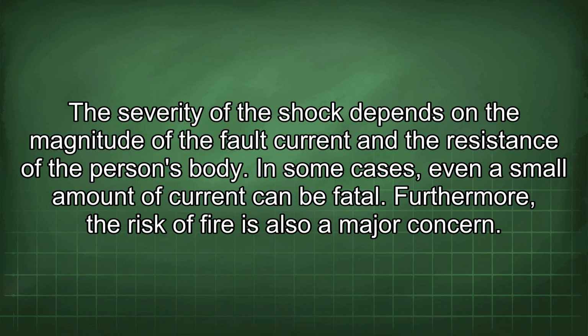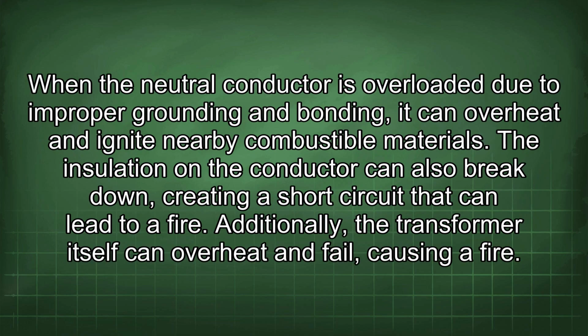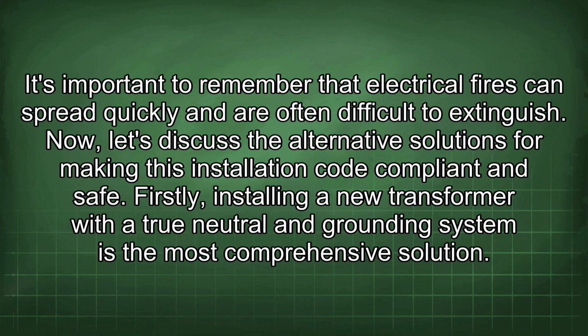Furthermore, the risk of fire is also a major concern. When the neutral conductor is overloaded due to improper grounding and bonding, it can overheat and ignite nearby combustible materials. The insulation on the conductor can also break down, creating a short circuit that can lead to a fire. Additionally, the transformer itself can overheat and fail, causing a fire. It's important to remember that electrical fires can spread quickly and are often difficult to extinguish.